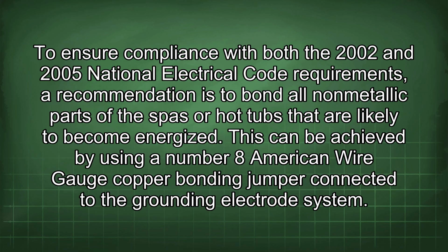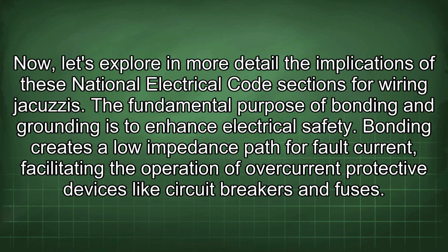To ensure compliance with both the 2002 and 2005 National Electrical Code requirements, a recommendation is to bond all non-metallic parts of the spas or hot tubs that are likely to become energized. This can be achieved by using a number 8 American wire gauge copper bonding jumper connected to the grounding electrode system. Now let's explore in more detail the implications of these National Electrical Code sections for wiring jacuzzis.